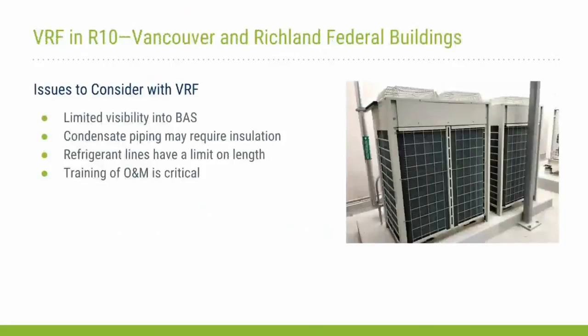So some of the issues that I've seen with this installation and others prior to joining the agency, we talked about the limited visibility into the BAS and the black box that both Robert and Roger had talked about in depth, so I won't go into it. It makes it tricky when you try to do any sort of commissioning, of course, trying to see what's in the system. You're giving a set point and maybe you're having an alarm coming back, but other than that, you can't really interrogate the system very much.